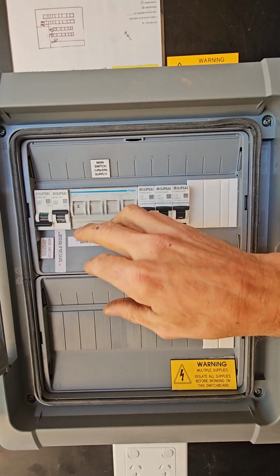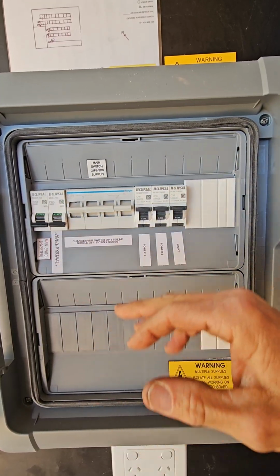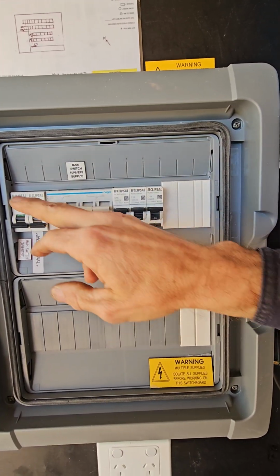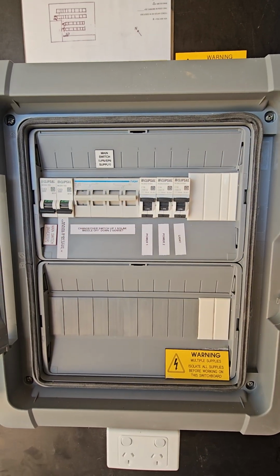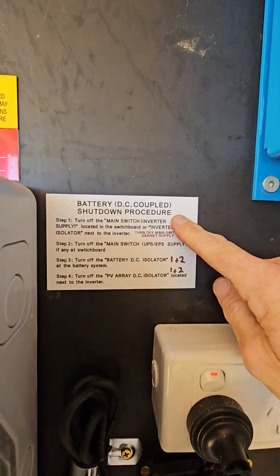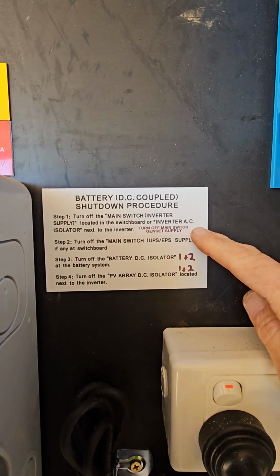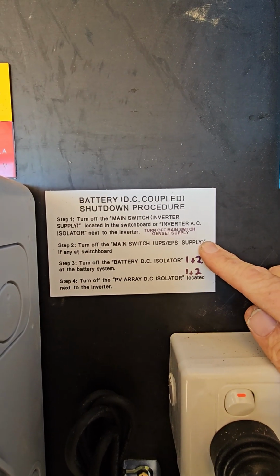If there's something wrong with the system and you can't get it going at the time, we'll put that back to the off position. So that's the first 3 parts of the shutdown: main switch inverter is off, main switch generator supply is off, main switch UPS EPS supply is off.